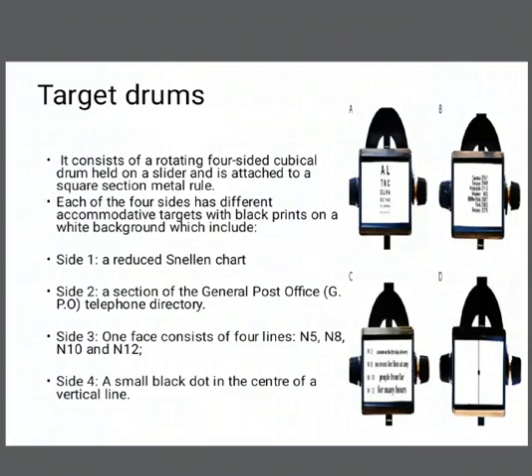The target drums consist of a rotating four-sided cubicle drum held on a slider, and the slider is attached to the square rule. Each of the four sides has different accommodative targets with black print on a white background, such as a reduced Snellen chart on side one as seen in figure A, a section of a general post office telephone directory on side two as seen in figure B, and a print of N5, N8, N10, and N12 on side three as seen in figure C, and a small black dot in the center of a vertical line on side four as seen in figure D.